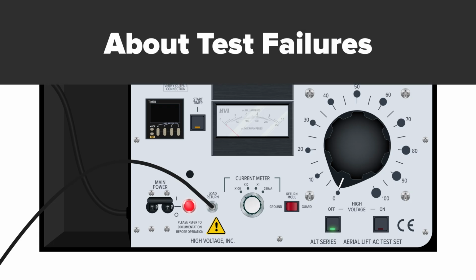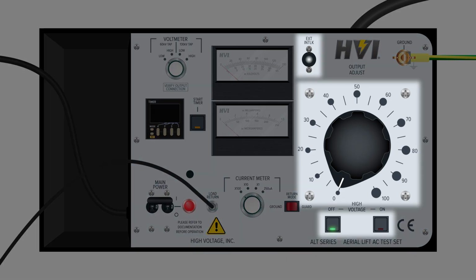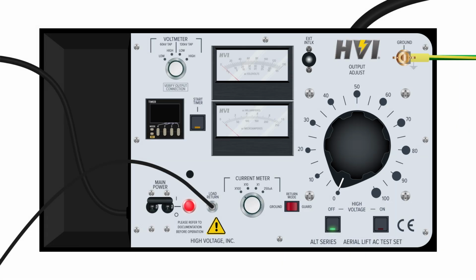About test failures. ALT series Hipots feature an internal overload relay as one final safety feature. The relay is found in the primary circuit and is sensitive to primary current overloads. The overload is set to 120% of the rated output. Anything beyond the overload limit, and the relay will power down the high voltage circuit to protect the device and personnel.